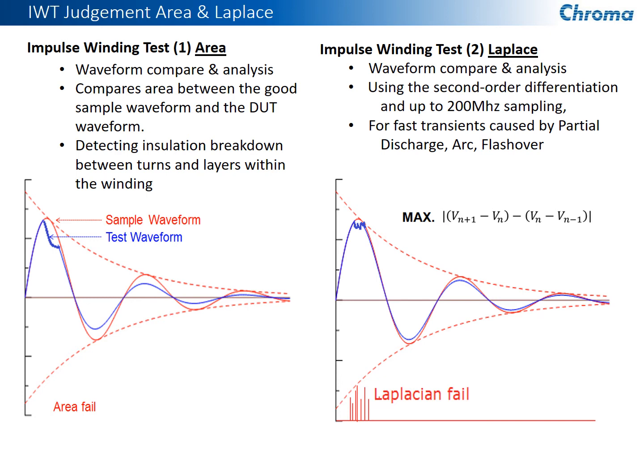And then again, as we mentioned earlier, the impulse winding test, doing the Laplace test, looks for faster transients such as partial discharge, arc and flashover, and that would occur with a very fast transient, a very short interruption of the waveform that would indicate one of these types of failures. And we can do that measurement by using what's referred to as a second order differentiation, and also a very high sampling rate, up to 200 megahertz, of all the data points that make up the waveforms.